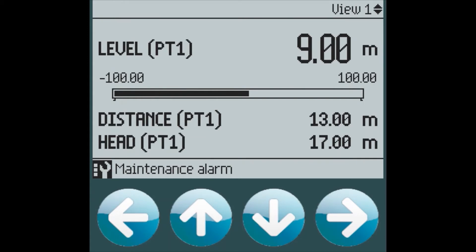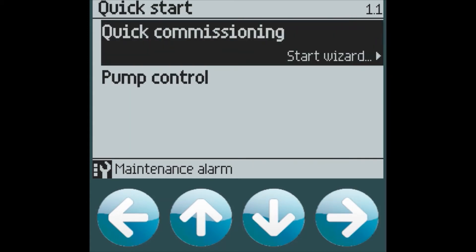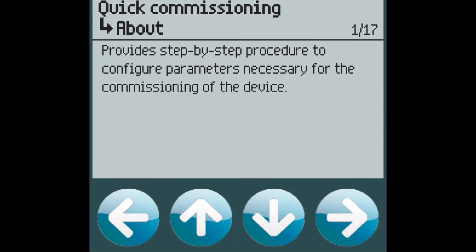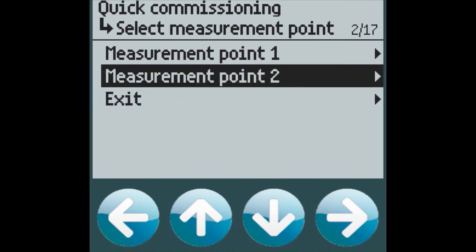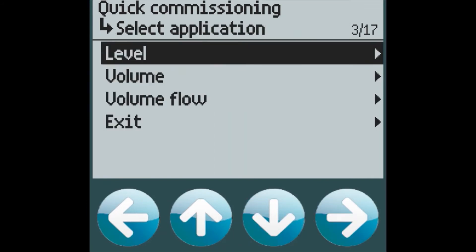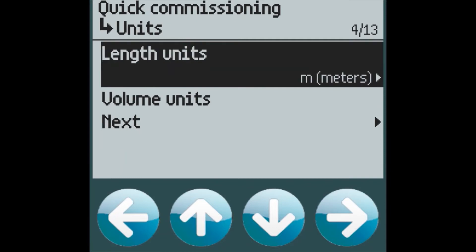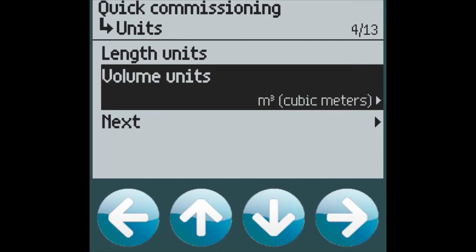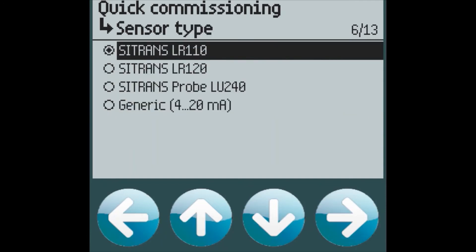Now let's set up our second application. Again we go into Quick Start and Quick Commissioning, and measurement point 2. This time we're going to do a volume application. We still need to set our length units and our volume units, and move on to the next section. This time let's choose a Sitrans LR110.